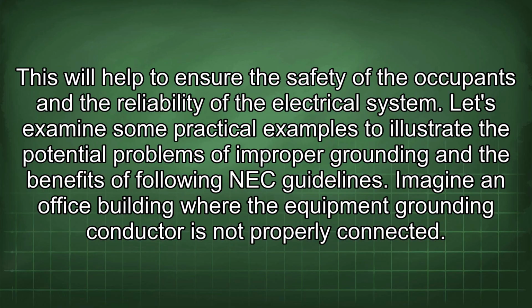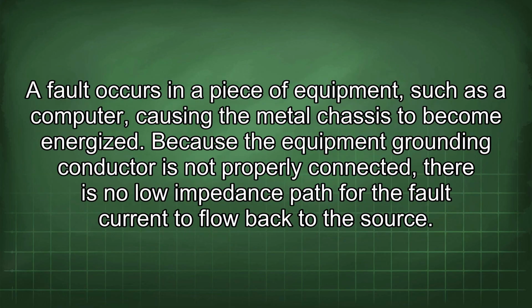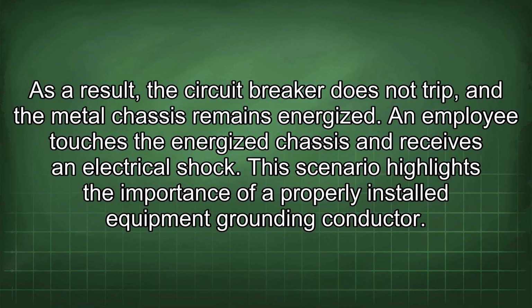Let's examine some practical examples to illustrate the potential problems of improper grounding and the benefits of following NEC guidelines. Imagine an office building where the equipment grounding conductor is not properly connected. A fault occurs in a piece of equipment, such as a computer, causing the metal chassis to become energized. Because the equipment grounding conductor is not properly connected, there is no low impedance path for the fault current to flow back to the source. As a result, the circuit breaker does not trip, and the metal chassis remains energized. An employee touches the energized chassis and receives an electrical shock. This scenario highlights the importance of a properly installed equipment grounding conductor.